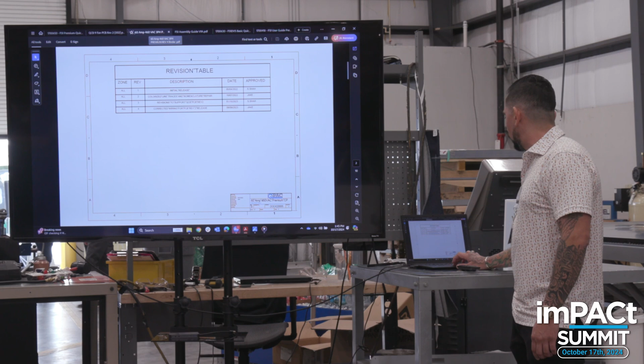Once you pull the guts out of the unit, the shaft is gone, the housing is gone, the base is gone, whether it's spring or inertia. As soon as you get that out, you have a nice clean surface all the way around the unit. You install your perimeter angle, and then the rest just goes in like butter. You install one panel, then the second, then the third, going in order. The diagram lays it out nicely and makes it very simple to install.